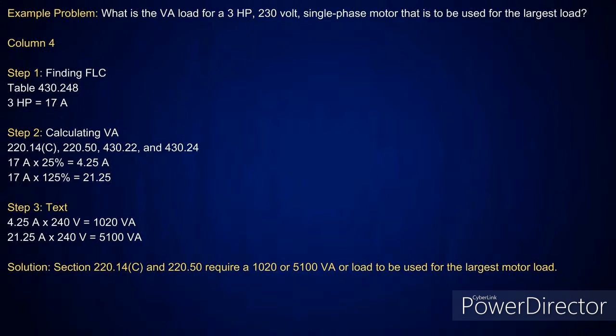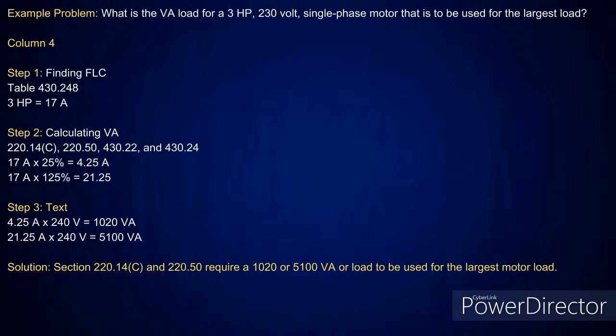Do you want EVSE? What you're getting into, the 125%, that's for the branch circuit. That's totally different than dealing with the full calculation here. Okay? And because we're setting this in and dealing with this right now in the fixed appliance load. Now, when you get into the full calculation, especially commercial, if it's a continuous load, you have to take it at what? 125%. So you would have to add that on there.